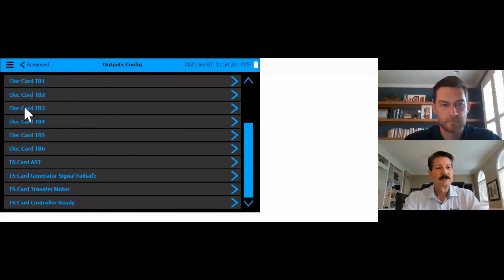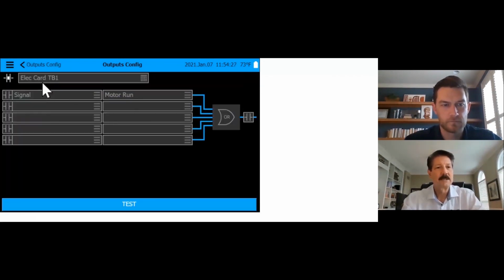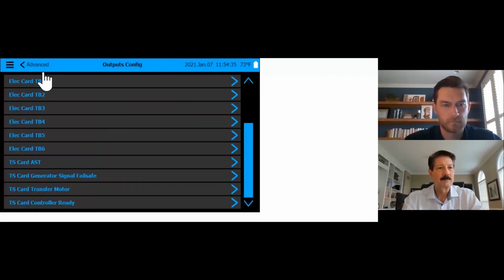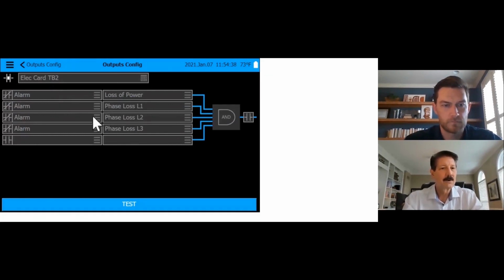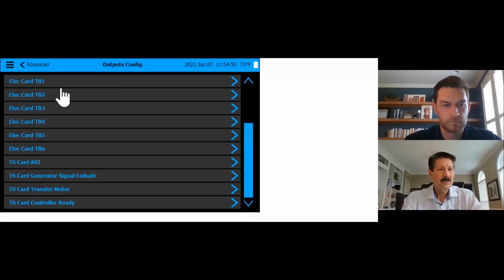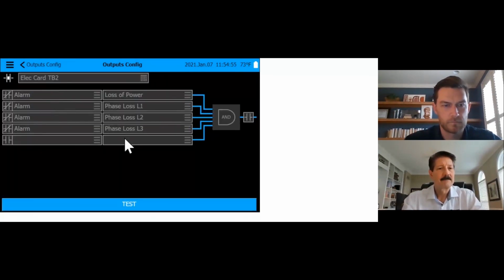All right, let's move into outputs. So TB1 through 6 are our remote alarm contacts. Again, those contacts are rated for 8 amps at 240 volts. And TB1, again, it's motor run, it's fixed, it's required by code. TB2 shows loss of power, phase loss, L1, 2, 3. It's locked, we can't touch this, it's required by code. TB3, normal power, phase reversal. Obviously, those three are the key: motor run, phase reversal, and loss of power.